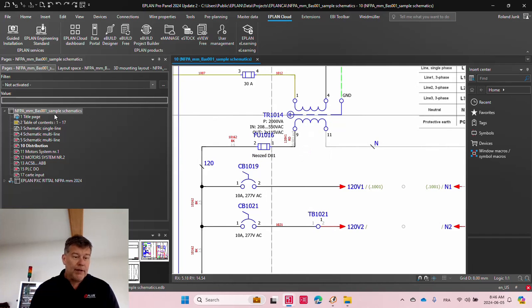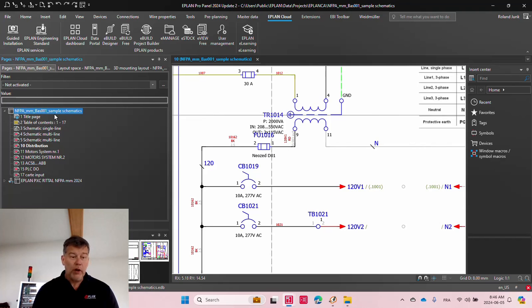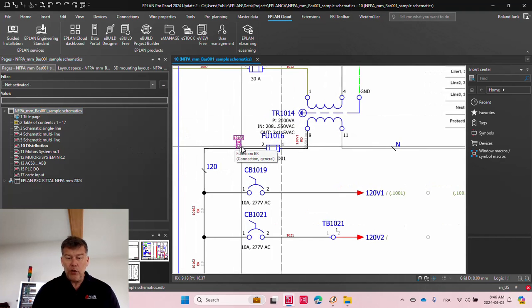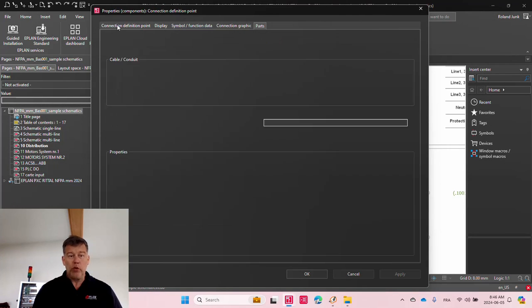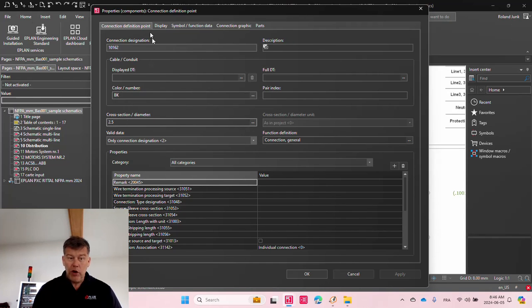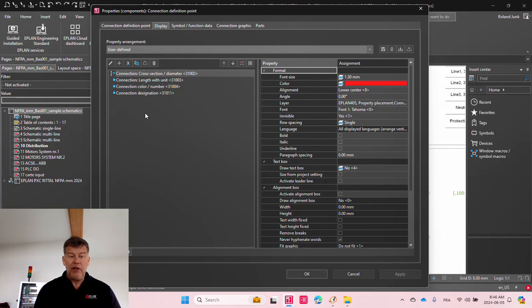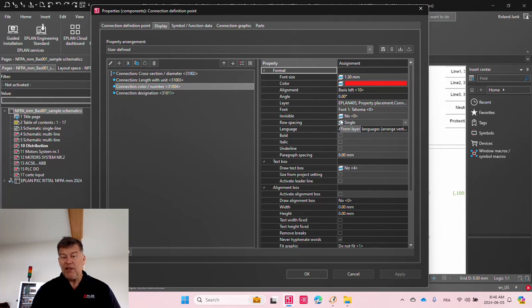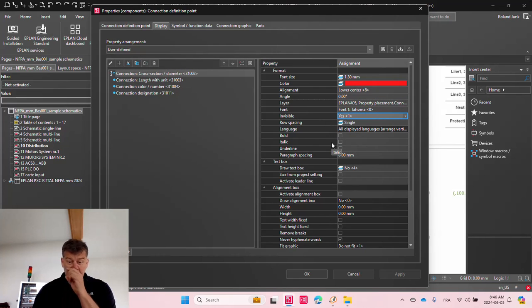One thing that I realized when I use the typical NFPA mm Bas001 templates and I create some schematics is that when I get to something like a wire designation or more a connection definition point, I do have, and I can assign a color, a gauge, which by the property arrangement will display it. Some of it may, because of the different layers set here, may be set to invisible, like the cross section, for instance, is set to be invisible.